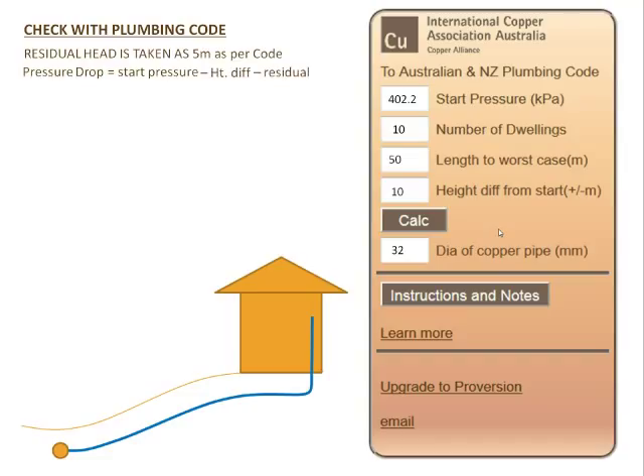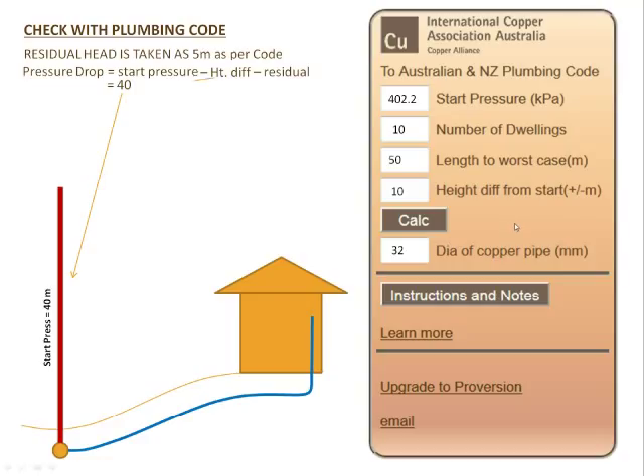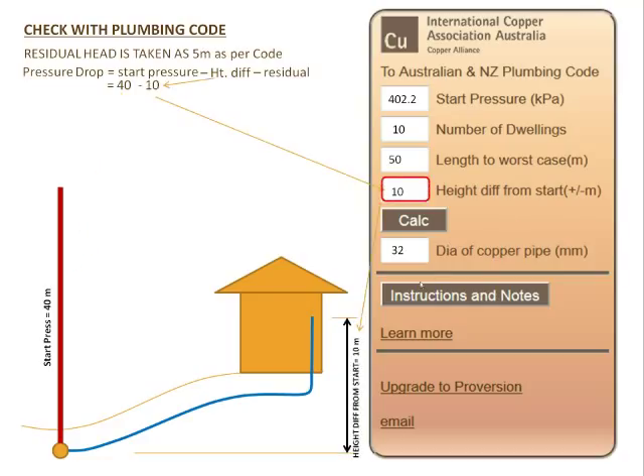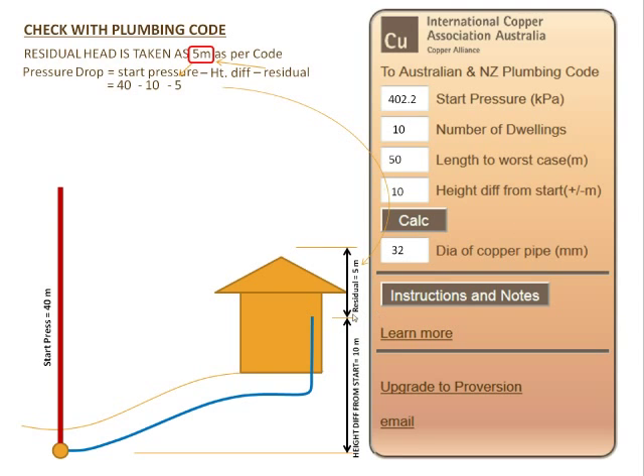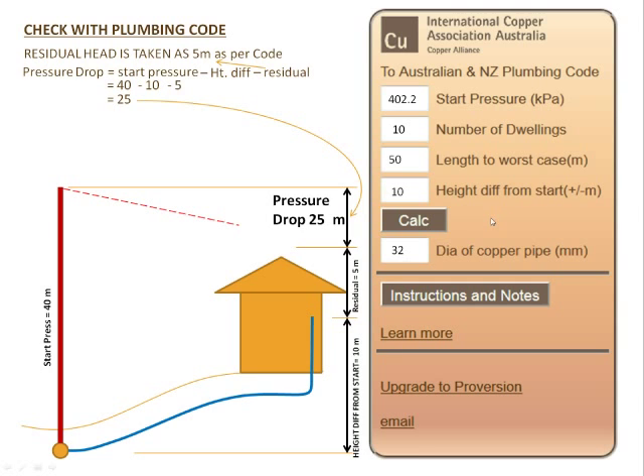The plumbing code requires us to find the pressure drop, which is the start pressure minus the height difference minus the residual head. Our start pressure was 40 meters, our height difference was 10 meters, and our residual head was 5 meters. We work out a pressure drop of 25 meters, and that's our hydraulic grade line.